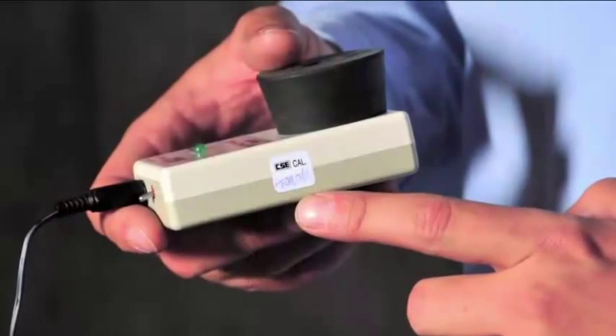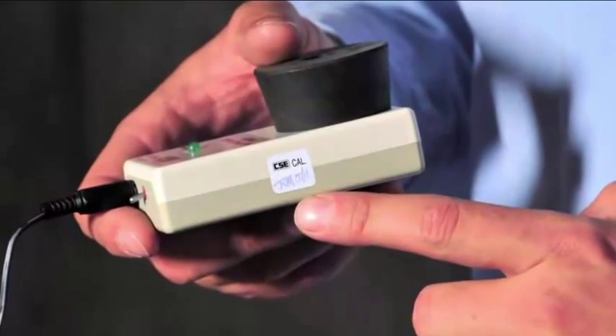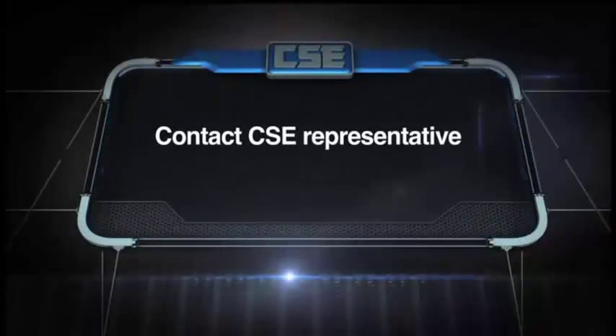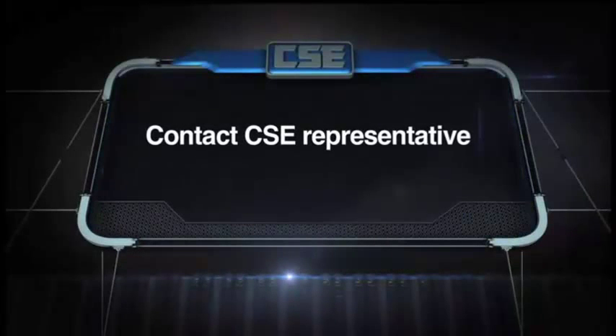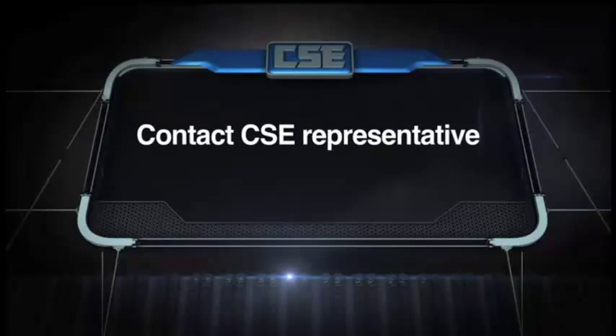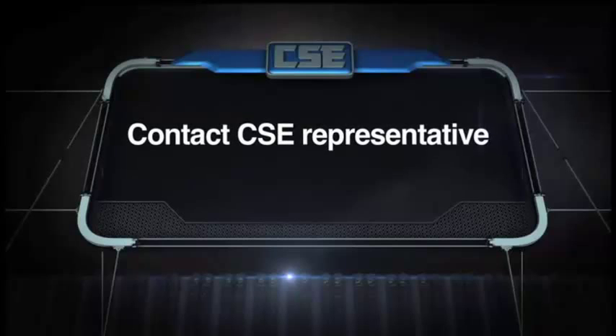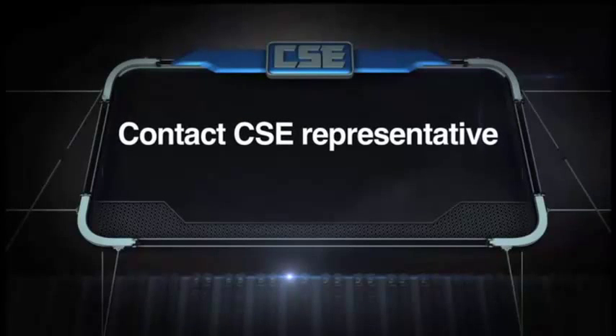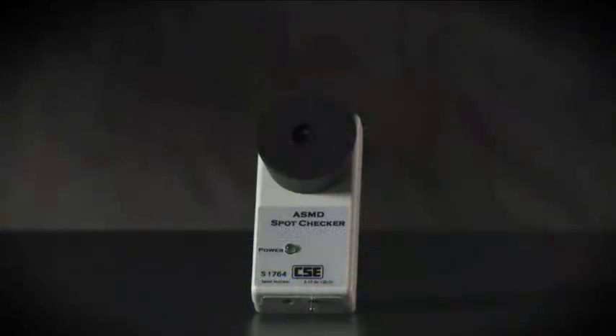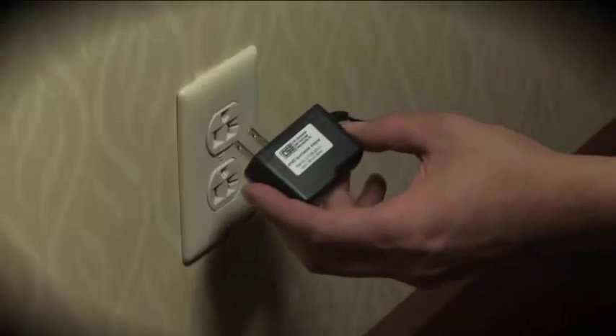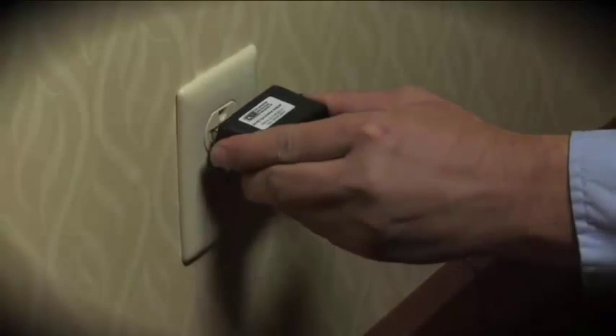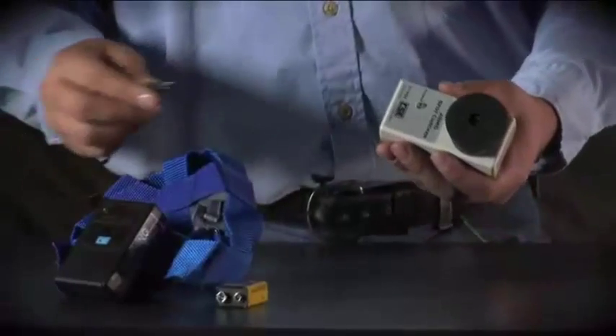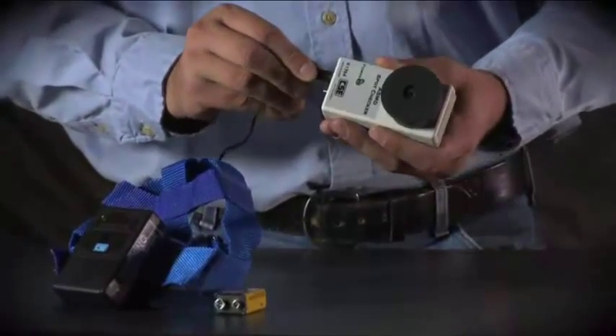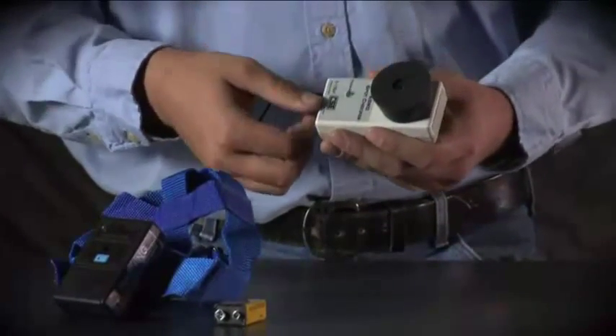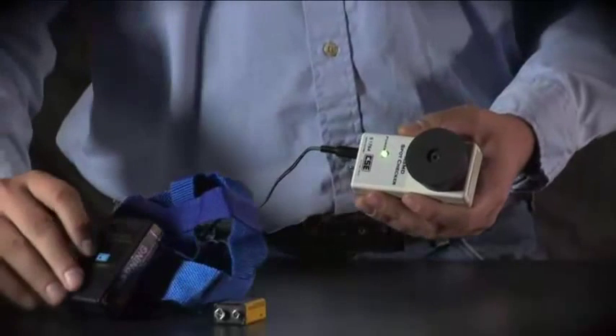Your spot checker should have been calibrated no more than 6 months ago. If the calibration date sticker is missing or not current, don't use the spot checker. Contact your CSE representative or send the spot checker back to CSE for calibration. If the calibration sticker is current, power up the spot checker. Plug its power adapter into a 120-volt outlet. Connect the power adapter cable to the socket in the spot checker's base. Flip the power switch on the spot checker's base to on.